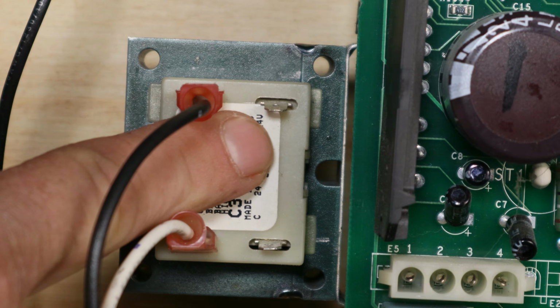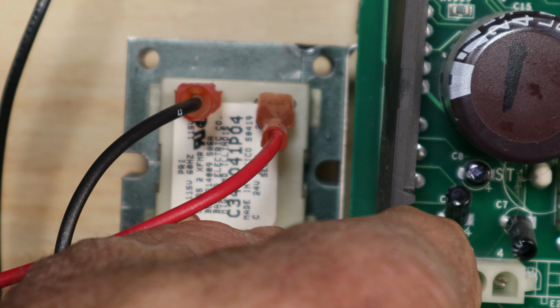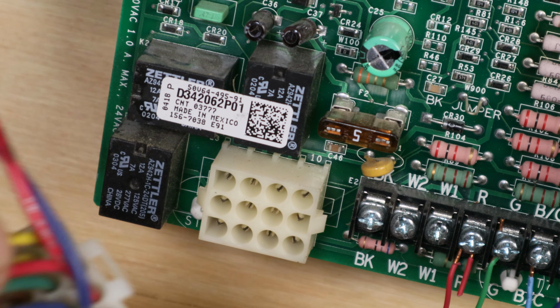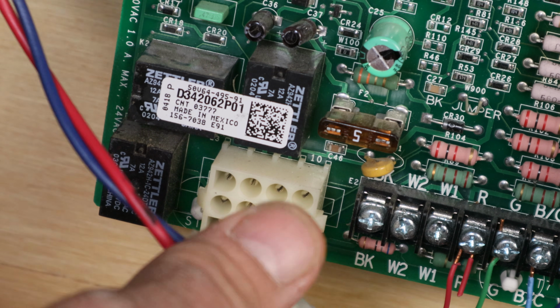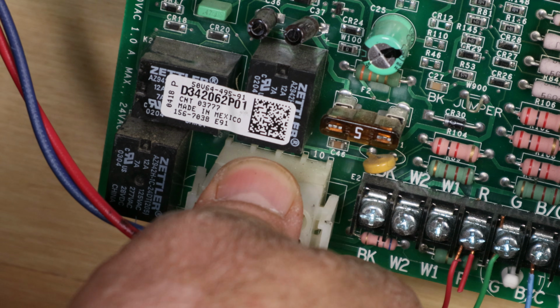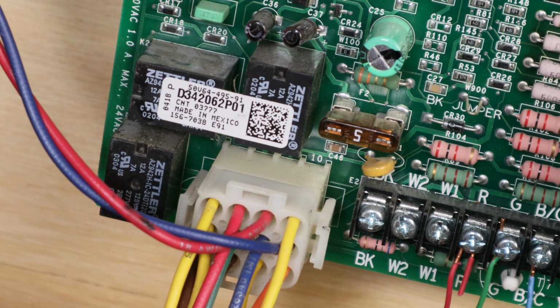So on the secondary side, I have 24 volts there. That is my connection. I'm going to connect that red wire on there. And this is my common. I'm going to put the blue on there. And then I'm going to go ahead and plug my Molex plug into the board. It only goes in one way. And that's it. We have our 24 volts for the whole control circuit.